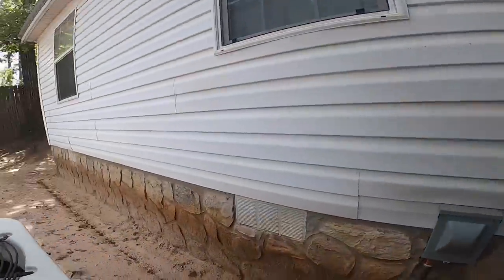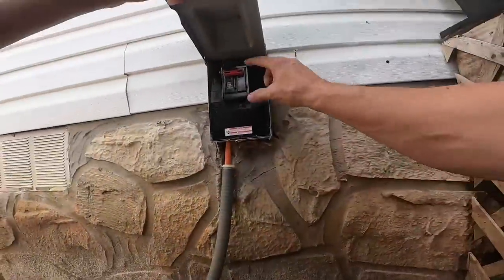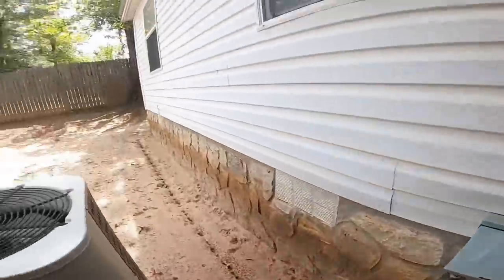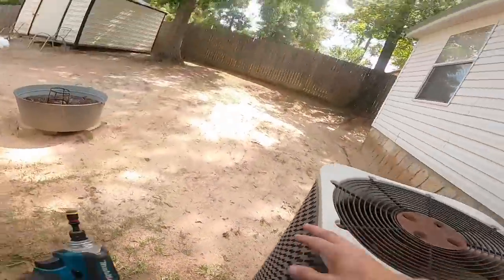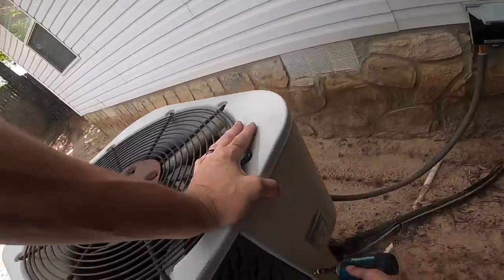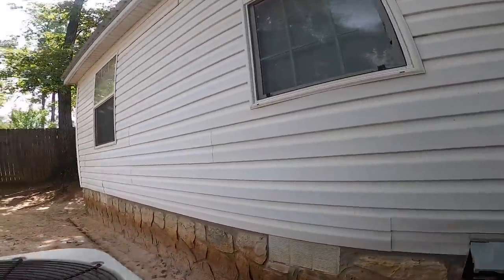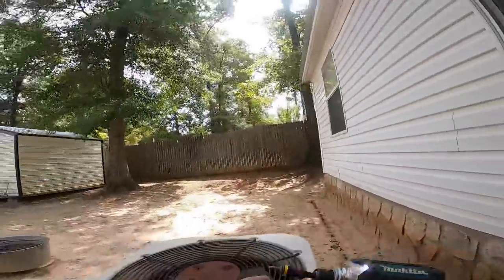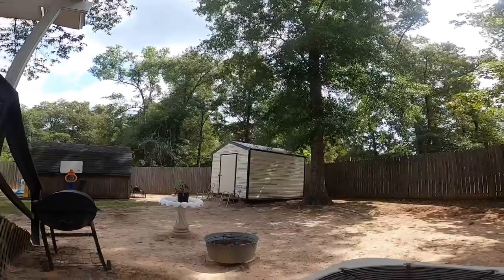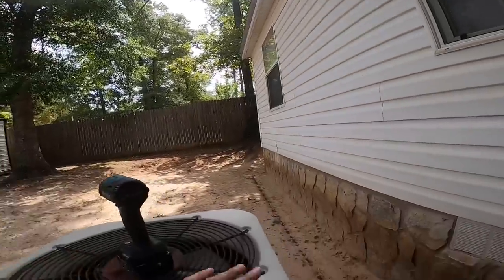All right, guys, on this one, I diagnosed stiff bearings actually last week, but I looked at the shaft and it looked like I may not be able to get it off, so I went and picked up a blade to go with it.